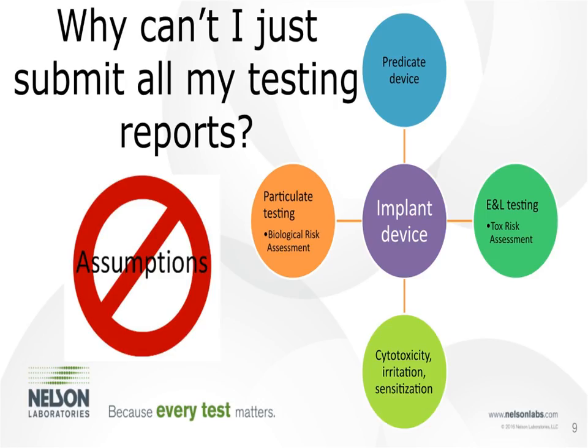This actually did happen where just testing reports were submitted and the regulatory agency came back and they had over 30 points that had to be addressed separately, noting that no connection was made for several points of testing that were submitted maybe under the predicate device, but there was no documentation to support that the predicate and the implant device were relatable. So projects can be complex, and it is important to summarize your findings and present your case to your reviewers.